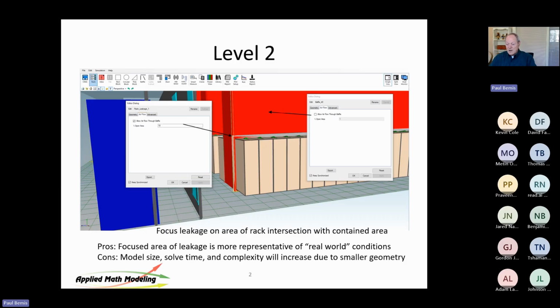Level two. So now level two here is focusing on the area of the intersection of the rack with the contained area. So I'm looking at right here. So here, I let this one now be set to no flow. By the way, don't use zeros in CFD. That's a mistake. Solvers don't like zeros. So we put switches in. So there's a switch right here that you can uncheck. It's normally checked. Uncheck it. That will make it a solid surface. It will not allow air to leak through it. So now I've sealed up this upper section.